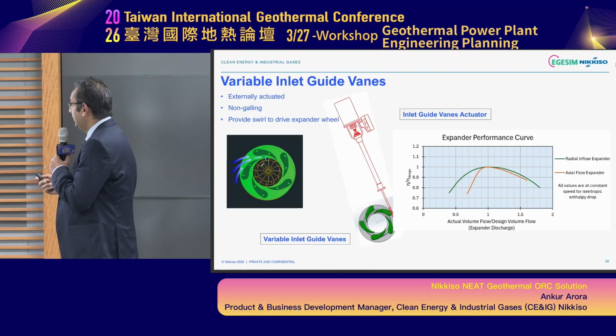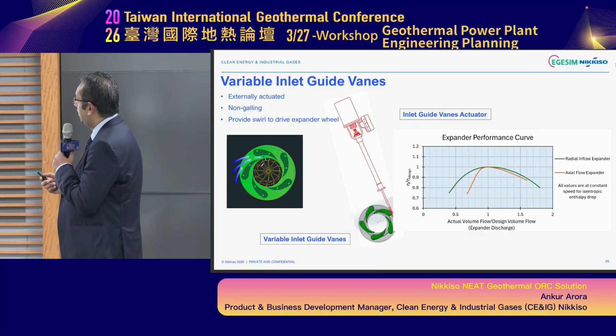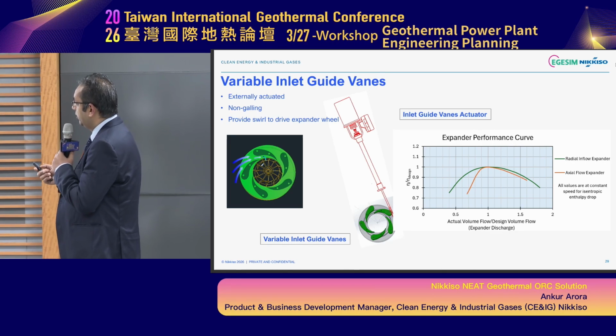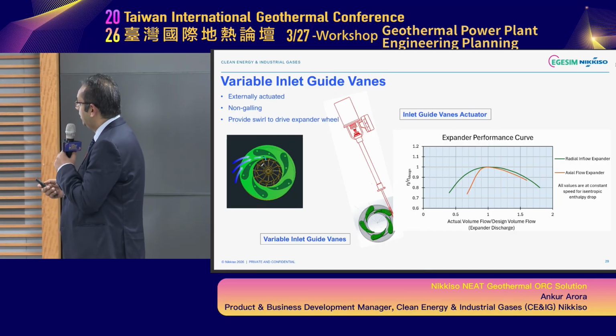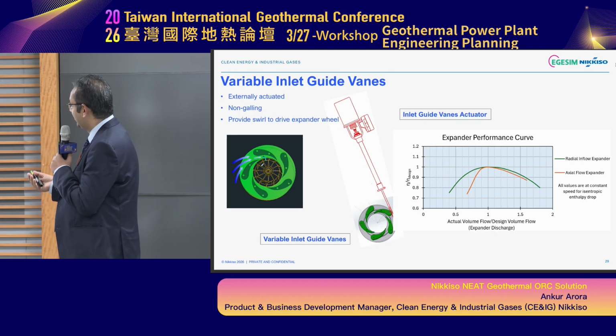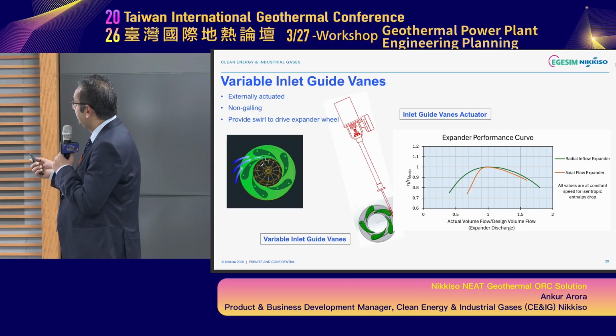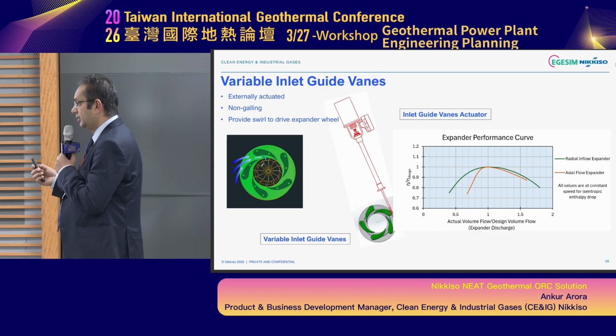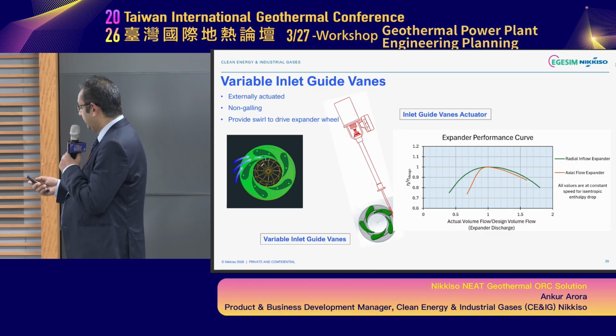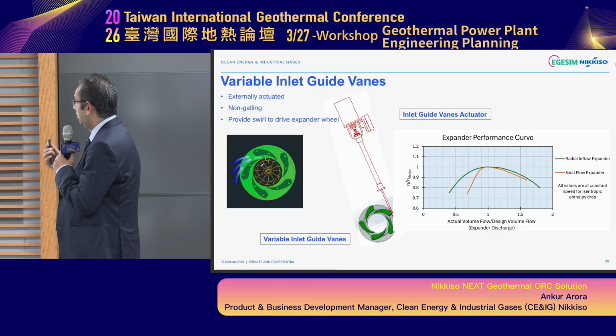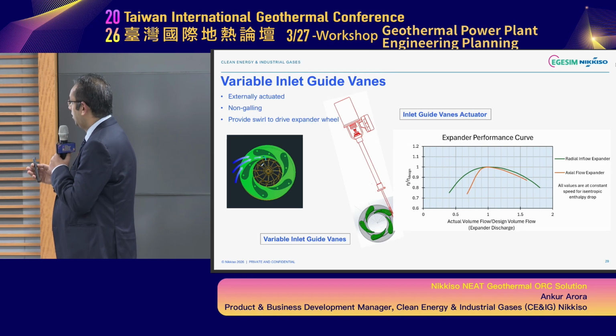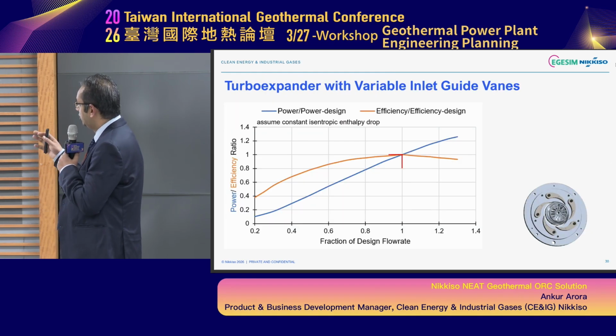These are variable inlet guided vane units, externally actuated, so there's no galling on the expander wheel. On the design side, using HYSYS, all manufacturers use more or less similar software, so at the design point everyone's efficiency is fairly similar. However, once you move away from the design point, that's where you see variation — for example if reservoir pressure drops, flow drops, or temperature changes — and you can manage those variations with the inlet guide vanes.